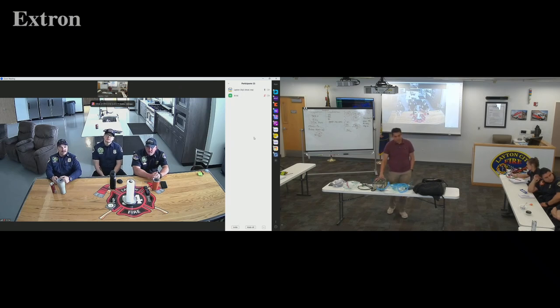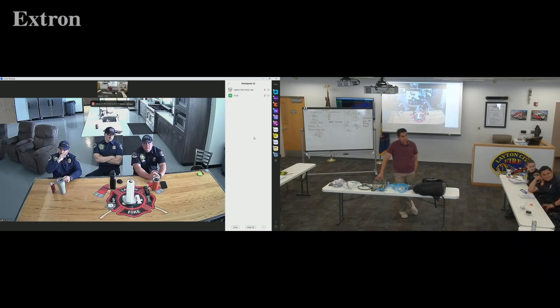So we get a baseline with those numbers on their ventilator that's been giving them good blood gas values, and then we switch over to ours. If we notice a change on our end tidal, then we can adjust our ventilator to get back to that baseline end tidal. That makes sense? So just take a second, throw on our equipment, and then that'll give us a little better idea, other than kind of swagging because we don't know, add a little bit here, add a little bit there, right? Then we can maintain what strategies they've been doing.